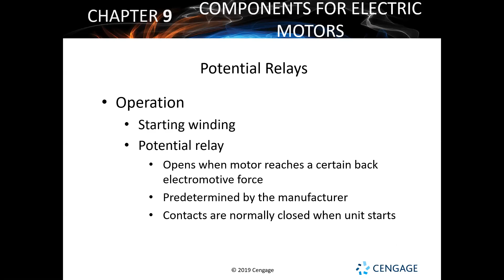So the only problem with it is sometimes there are some relays that will be time delayed or temperature delayed. You'll have a motor and, oh, the fan motor's starting but the compressor's not. Oh, that must be a bad compressor. Keep in mind, we've got relays that disconnect just because of the compressor getting too hot or not enough time going by between shutdown and turning on. So we got a lot of different ones.